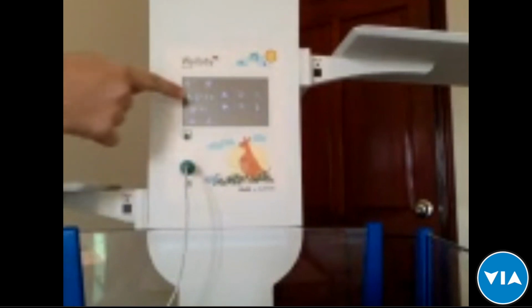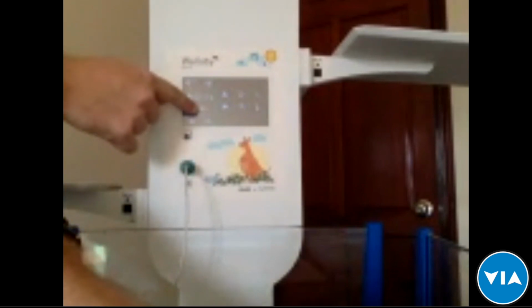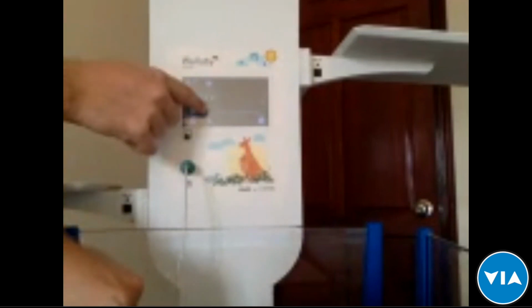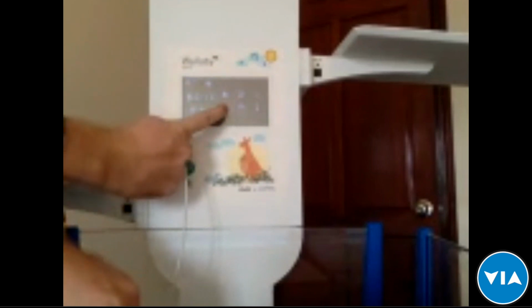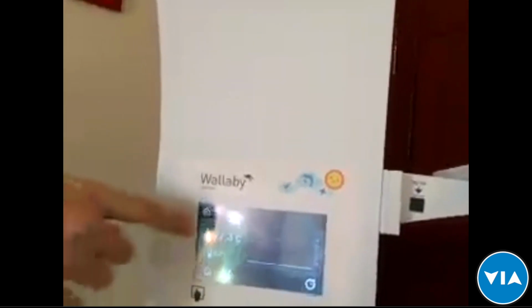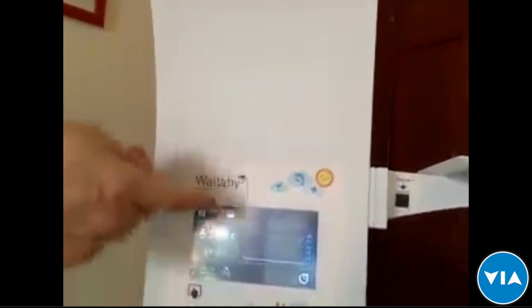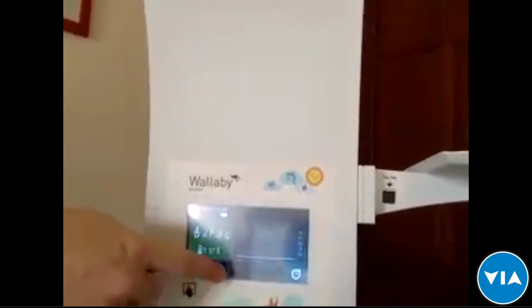Obviously, it's not the perfect way to control the temperature, but it's possible, with certain restrictions related to that mode. And the most popular and the most appropriate mode is the baby control mode, which is 36, according to the baby temperature detected by the skin sensor. And we have a set point that can be chosen. Here the room temperature is 25.7, and we can regulate up to what we need.